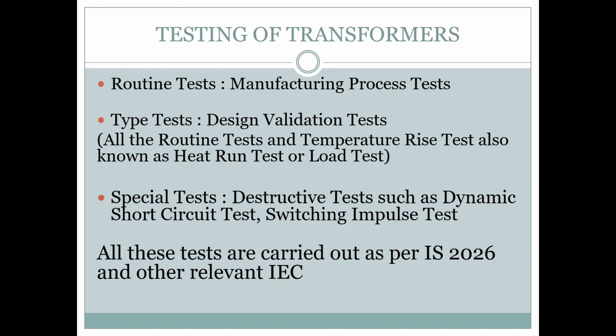Now, special tests are the destructive tests. That is called the dynamic short circuit test and the switching impulse test. Switching impulse test has now become a routine test for the high-level, 440 kV, 220 kV transformers. The short circuit test is like your heart failure. It can survive 3 short circuit tests, but it can fail at 1. But the interesting point is that the short circuit test is the validation of your design, that it has been made suitable for that particular fault level in the circuit, and it will be able to withstand it. Earlier it was for 1 second suitability, now it has gone up to 3 seconds. So the design has become much more critical again.